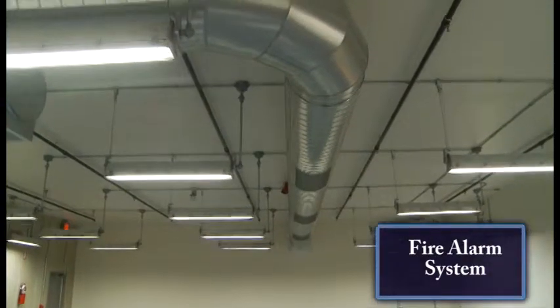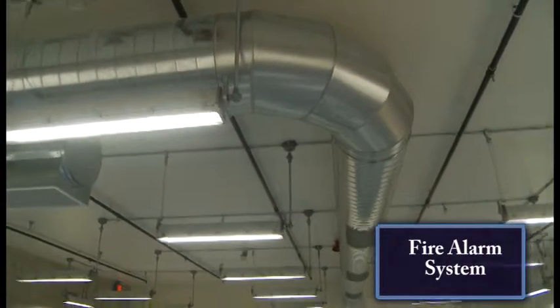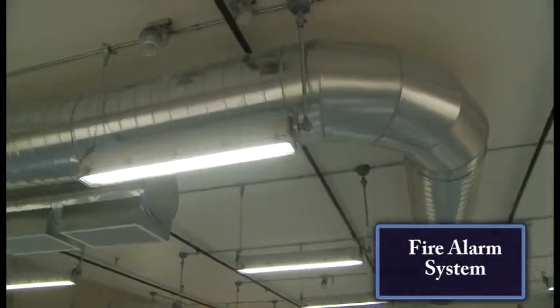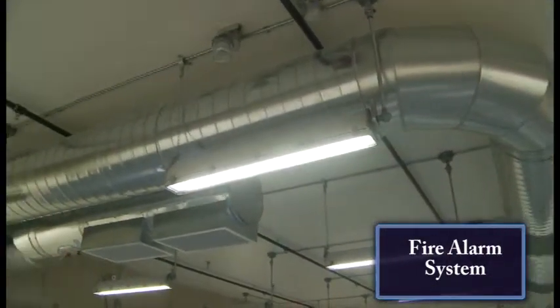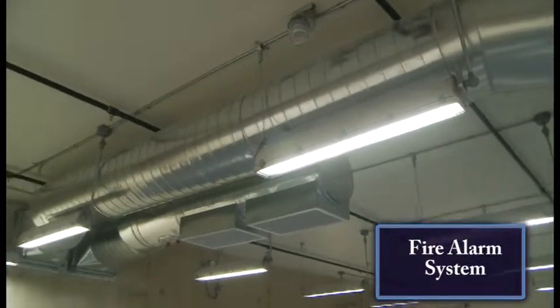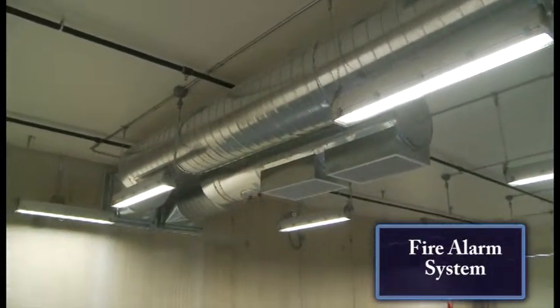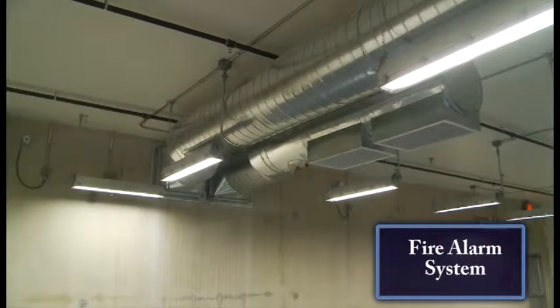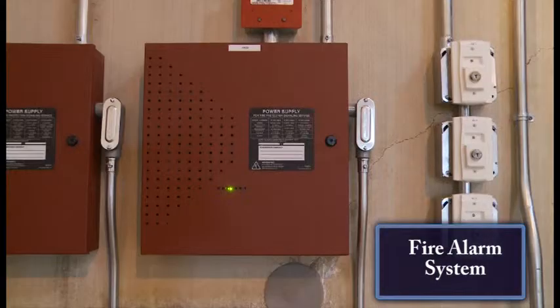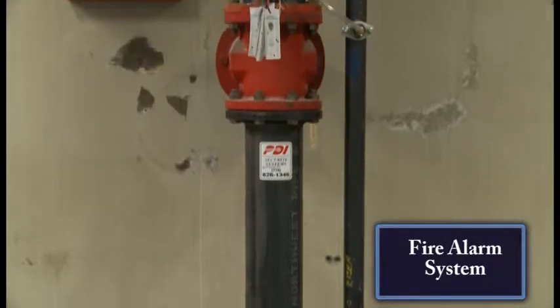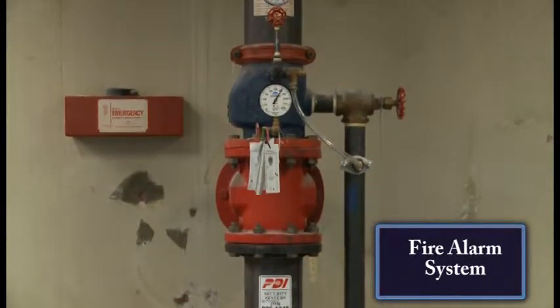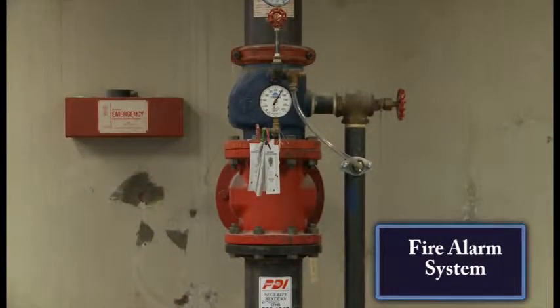Mechanical system monitoring includes duct-mounted smoke detectors to monitor supply-side ductwork of all HVAC air handlers moving more than 2,000 CFM. The duct smoke detectors are provided with remote test indicator and reset buttons. These are located in corridor areas outside the space served by the associated unit and prominently identified. The main sprinkler system and riser valves are provided with automatic monitoring of pressure, tamper, and flow status at the zone valve assembly.